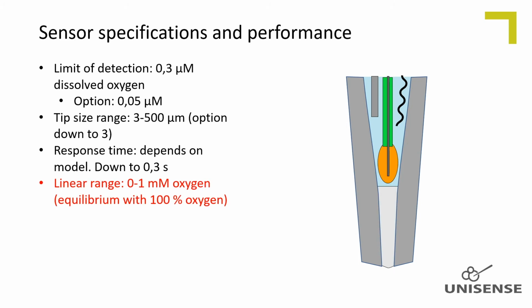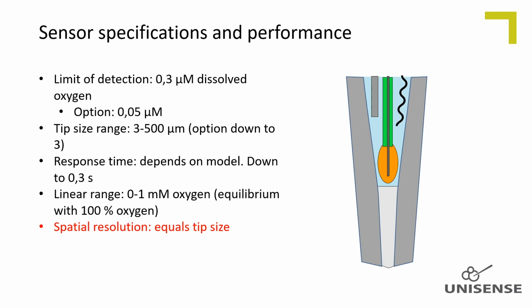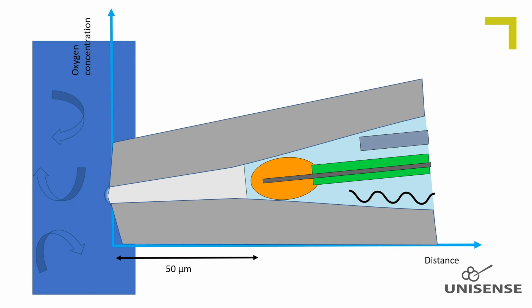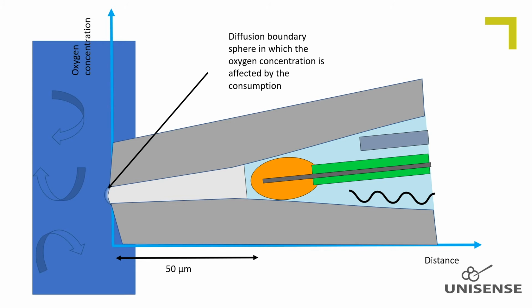Oxygen sensors respond linearly to oxygen concentrations. They respond linearly up to above 100% oxygen saturation, and even in supersaturated water or pressurized oxygen gas, the sensor responds linearly. The oxygen sensors can be applied with a spatial resolution which equals the tip diameter. This is just a rule of thumb because it cannot easily be validated. The sensor will sample oxygen from a very minute diffusion sphere at the membrane/sample interface.